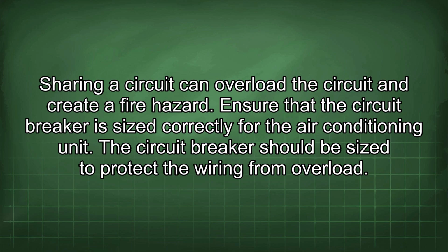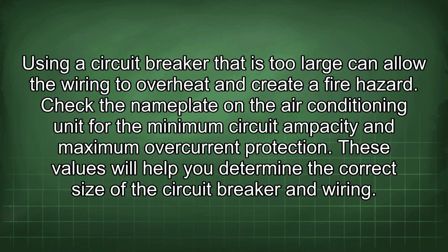Ensure that the circuit breaker is sized correctly for the air conditioning unit. The circuit breaker should be sized to protect the wiring from overload. Using a circuit breaker that is too large can allow the wiring to overheat and create a fire hazard. Check the nameplate on the air conditioning unit for the minimum circuit ampacity and maximum overcurrent protection. These values will help you determine the correct size of the circuit breaker and wiring.